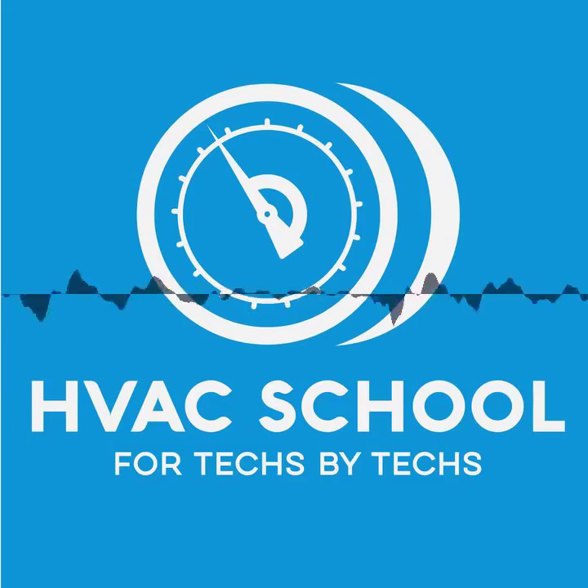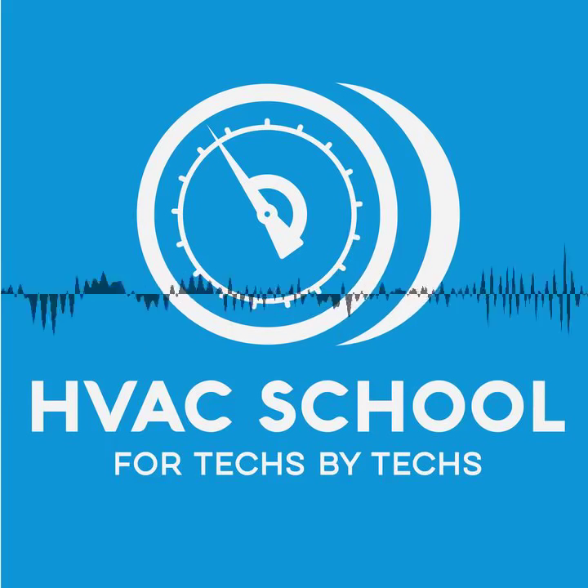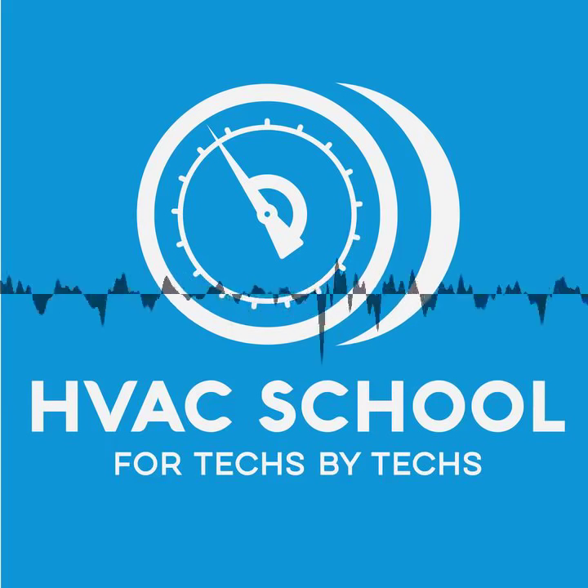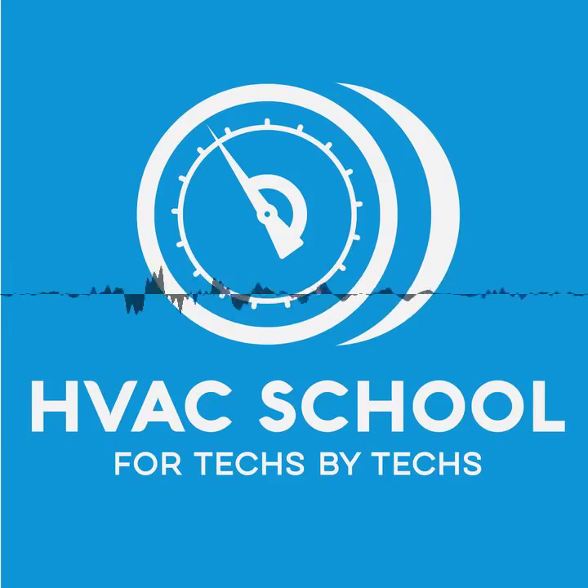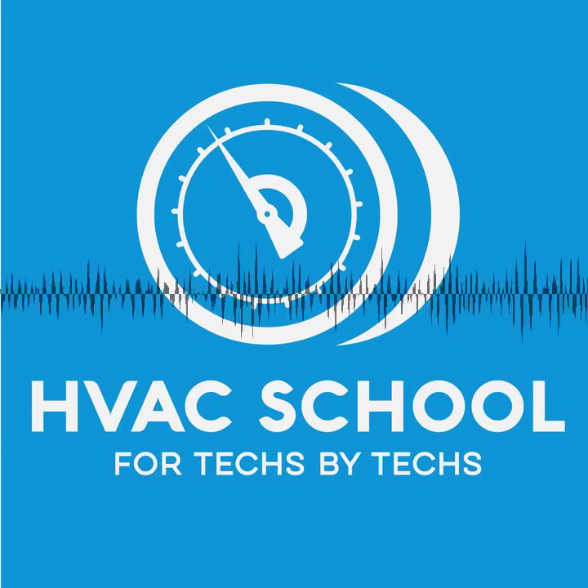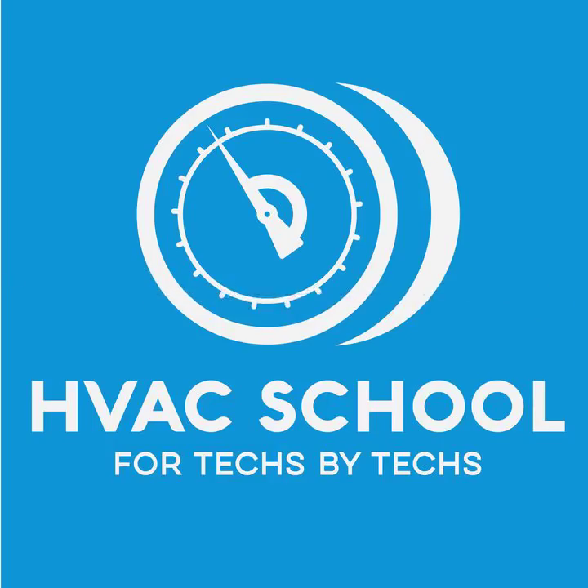When you start forcing your head pressure up on purpose so that your metering device works right, there's an energy hit there, in that you're increasing your compression ratio when you wouldn't have to. So a floating head pressure system, basically what you have to do to have that type of system is first you have to have a better metering device. If you have a metering device that doesn't require a minimum pressure difference, or requires a much lower minimum pressure difference, then you can let the head pressure go a lot lower, meaning that I can have a lower head pressure, a lower compression ratio, and use less energy to do the same amount of cooling.